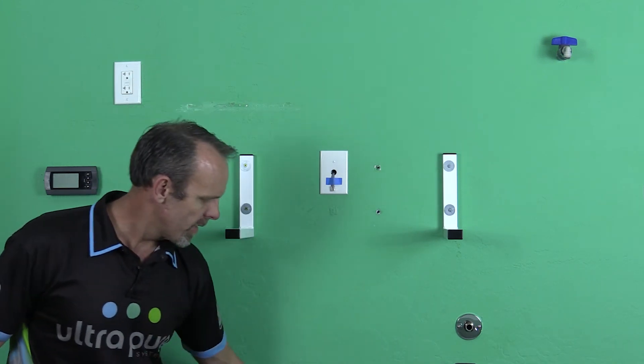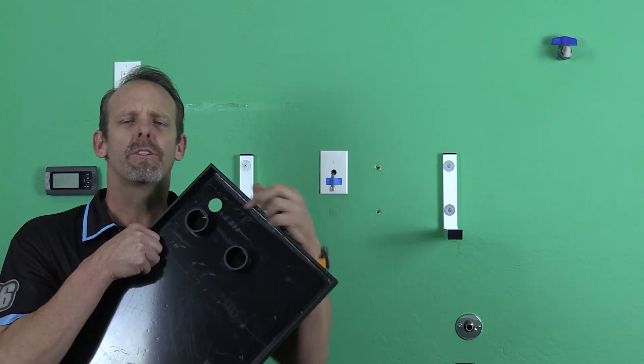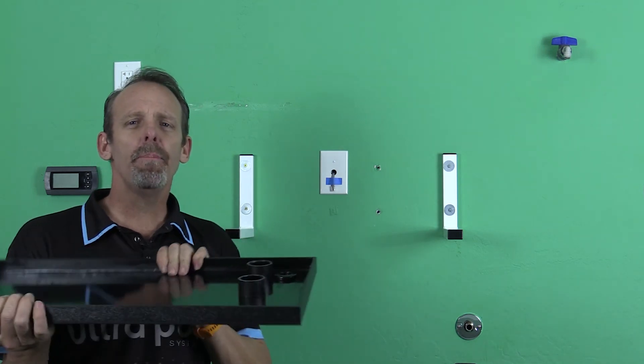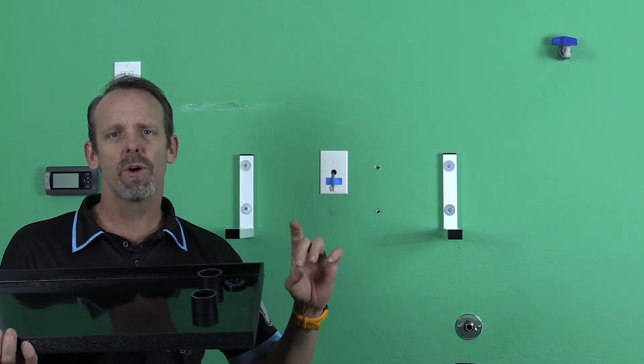Inside a clear bag, inside the clear bag, you'll have a bulkhead fitting. That bulkhead fitting is going to attach to the tray. In the corner, there's a larger hole. And that hole is where you will put the bulkhead fitting. It's very important that you put the bulkhead fitting from the top down. And then you'll want to put the nut on the bottom. At that point, the tray is going to serve as a safety water tray. It has standoffs on them so the humidifier doesn't set inside the pan. And then in the middle of the standoffs are where the bolts are going to go that we're going to squeeze the whole thing together.